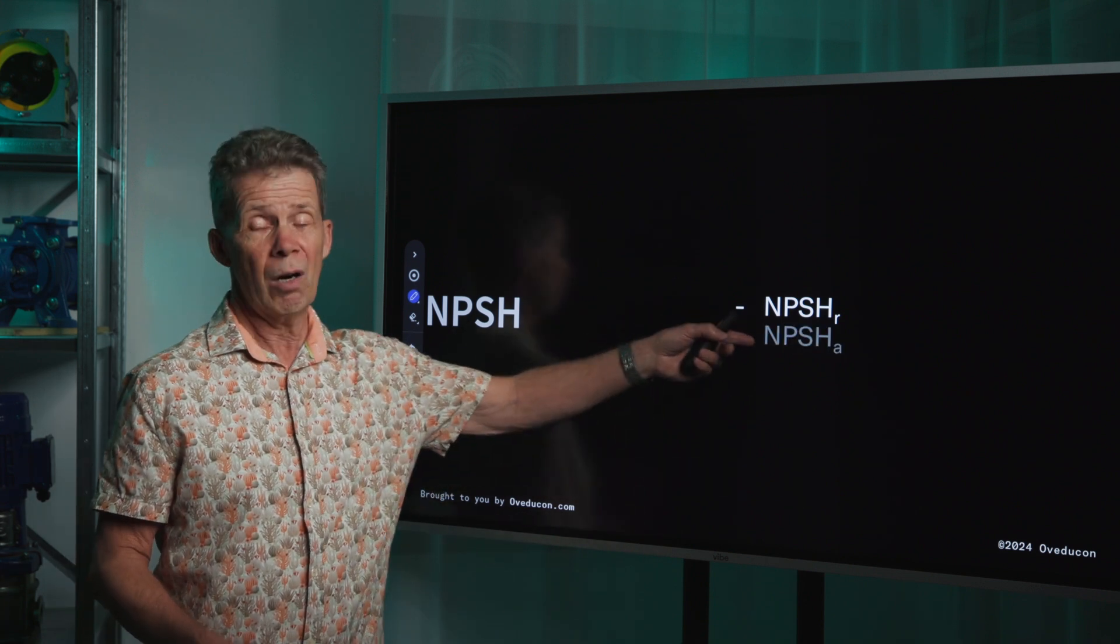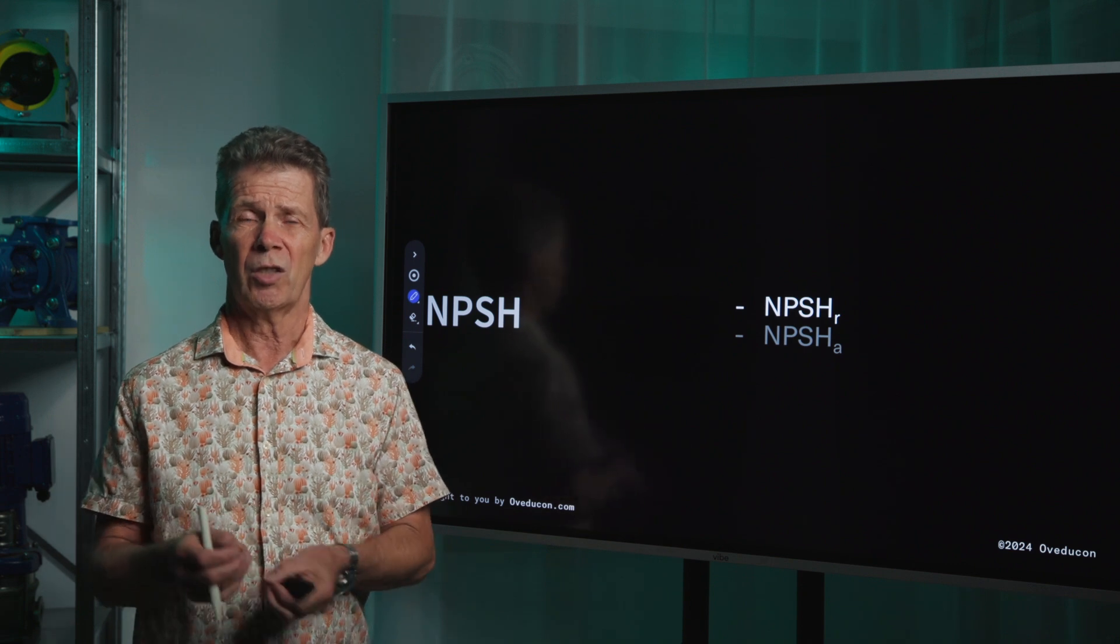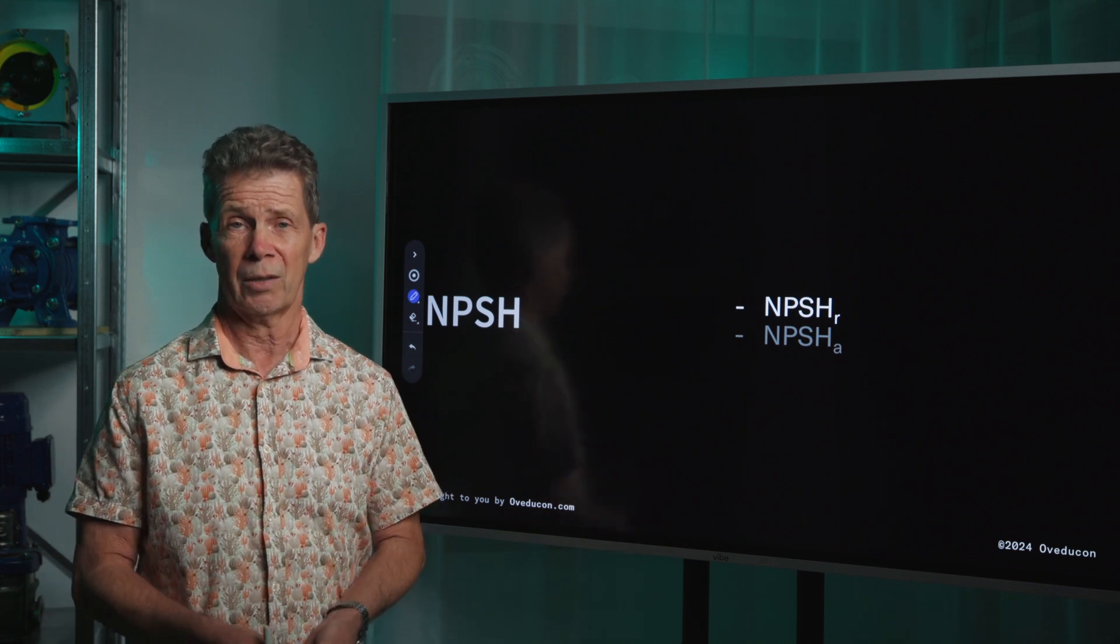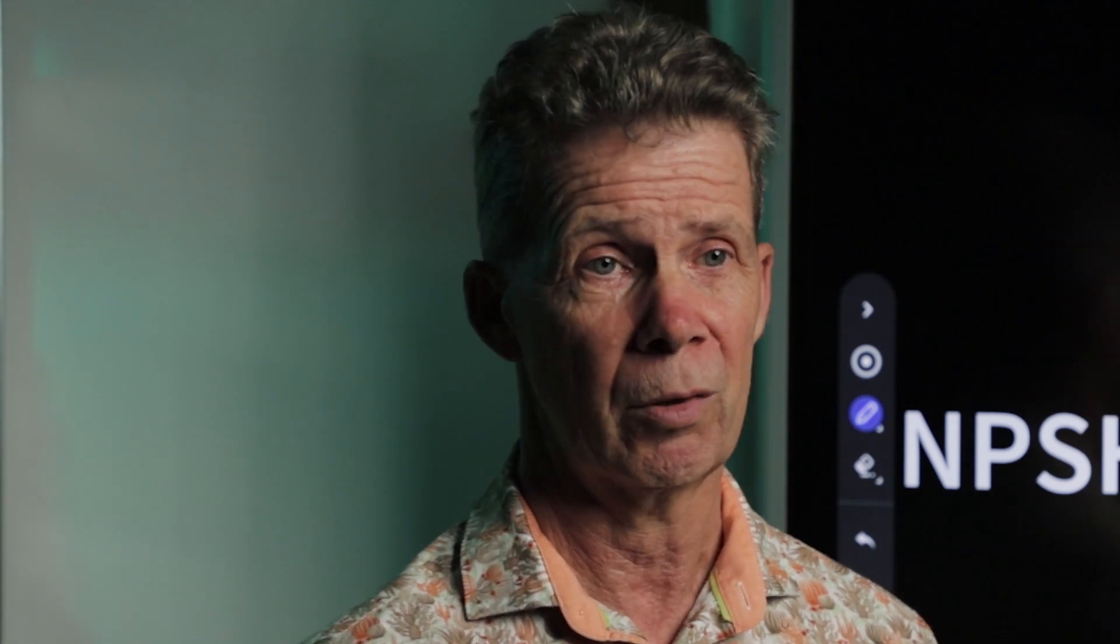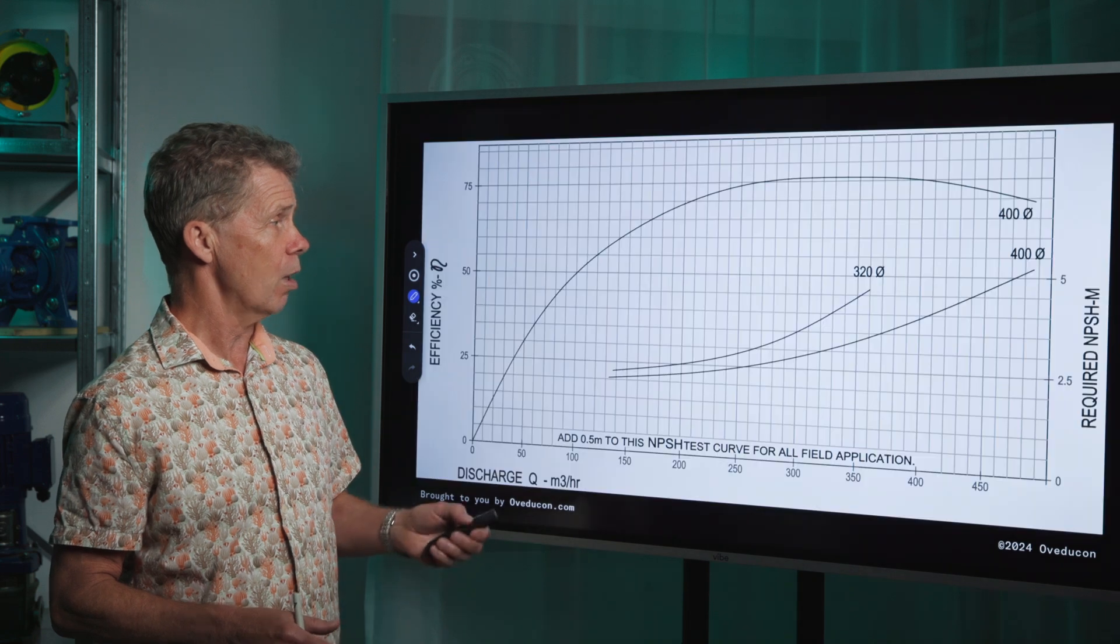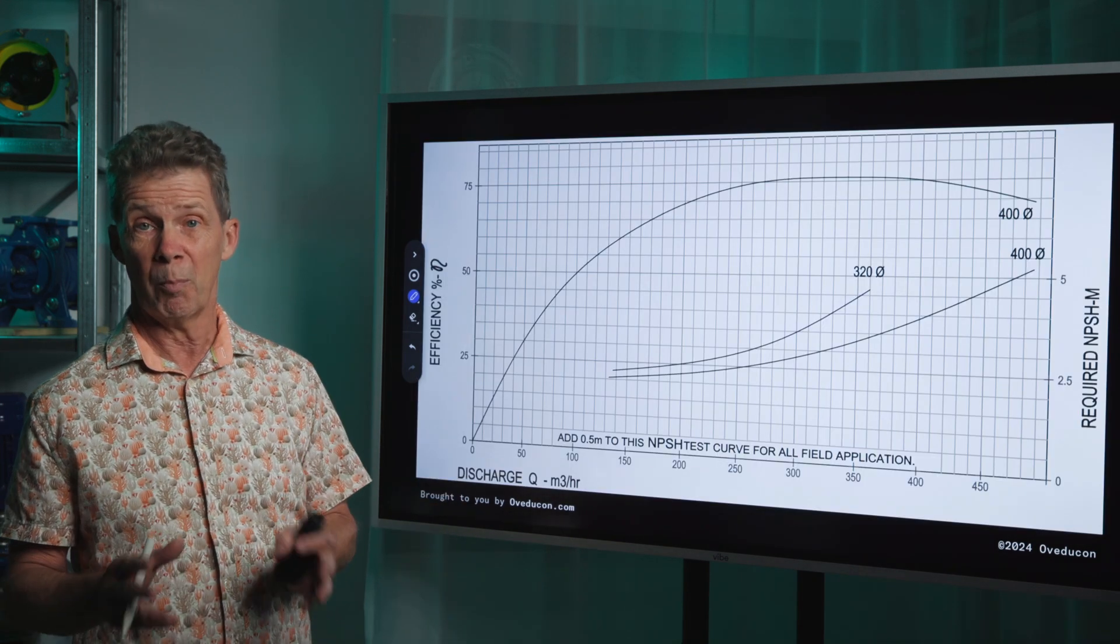The NPSH-R stands for net positive suction head required and that is the minimum pressure required at the suction port of the pump according to pump tests made by the pump manufacturer. The NPSH-R value is given in the pump curve.